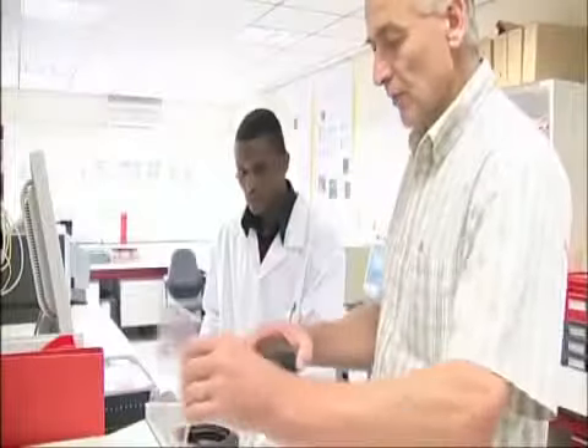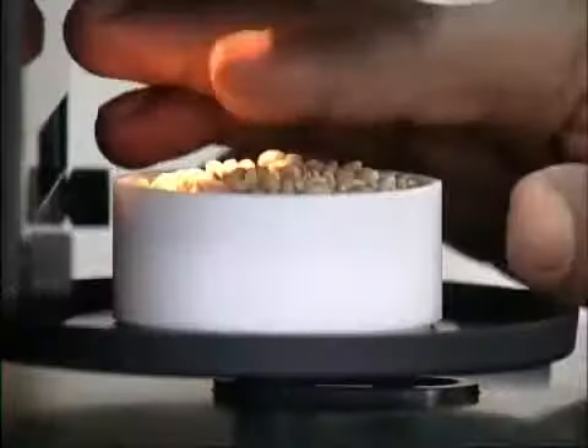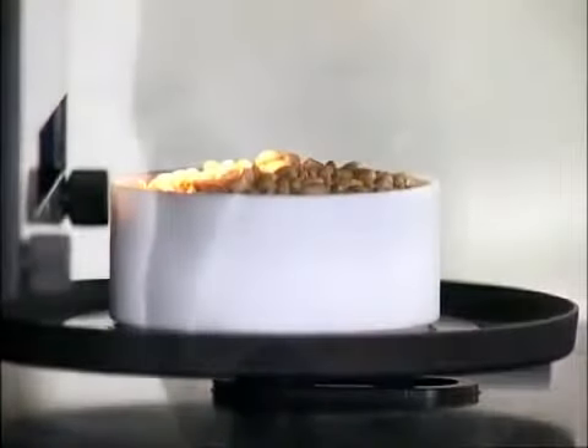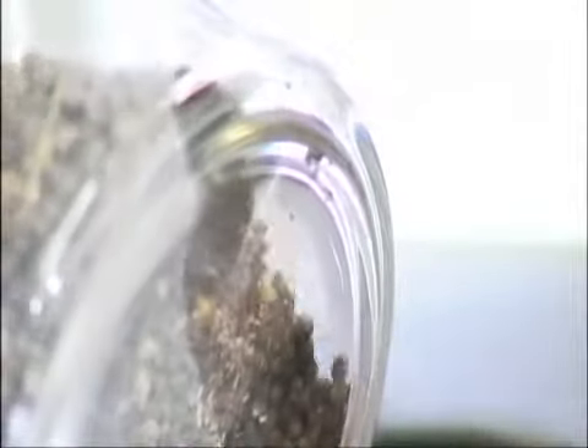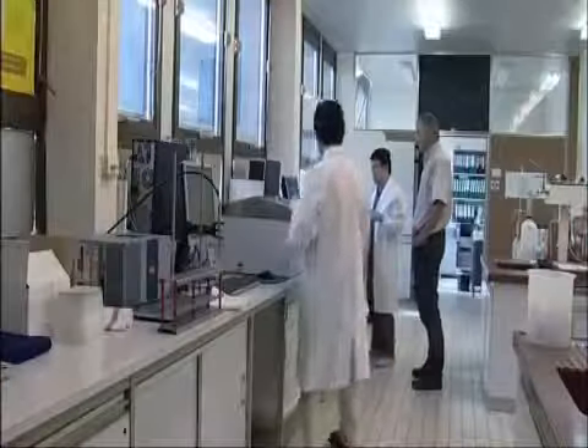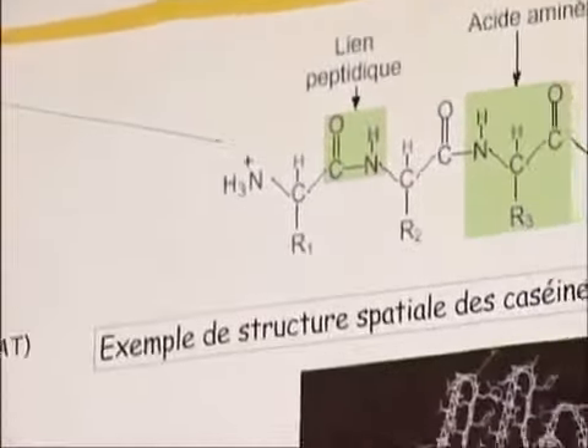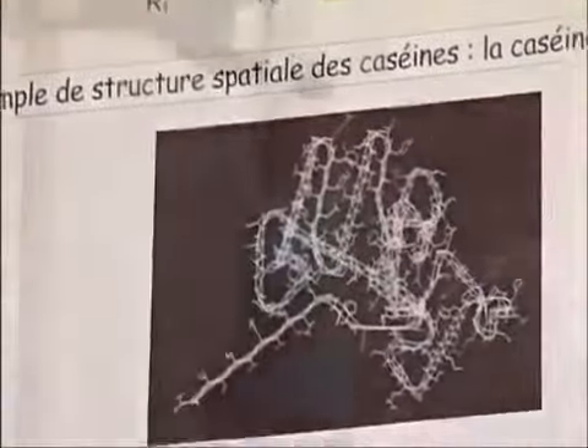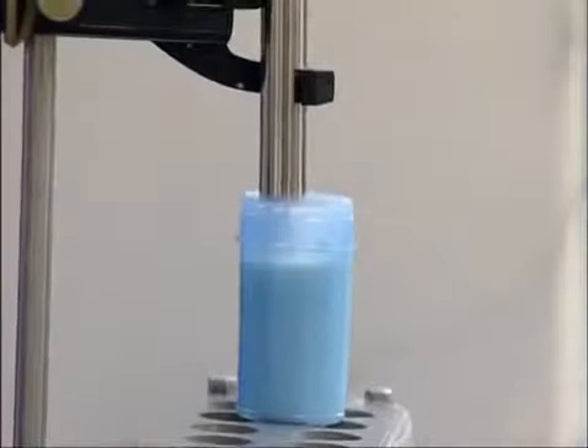We need calibration with NIR because the relationship between the matter and the light is specific by product, so you need to calibrate for each commodity. To calibrate, we need a reference method, and here in the lab we have most of the reference methods accredited by Belac in Belgium. We have also the NIR accredited, so we can do both. Reference method accredited, good calibration or good validation, and accreditation of the NIR too.